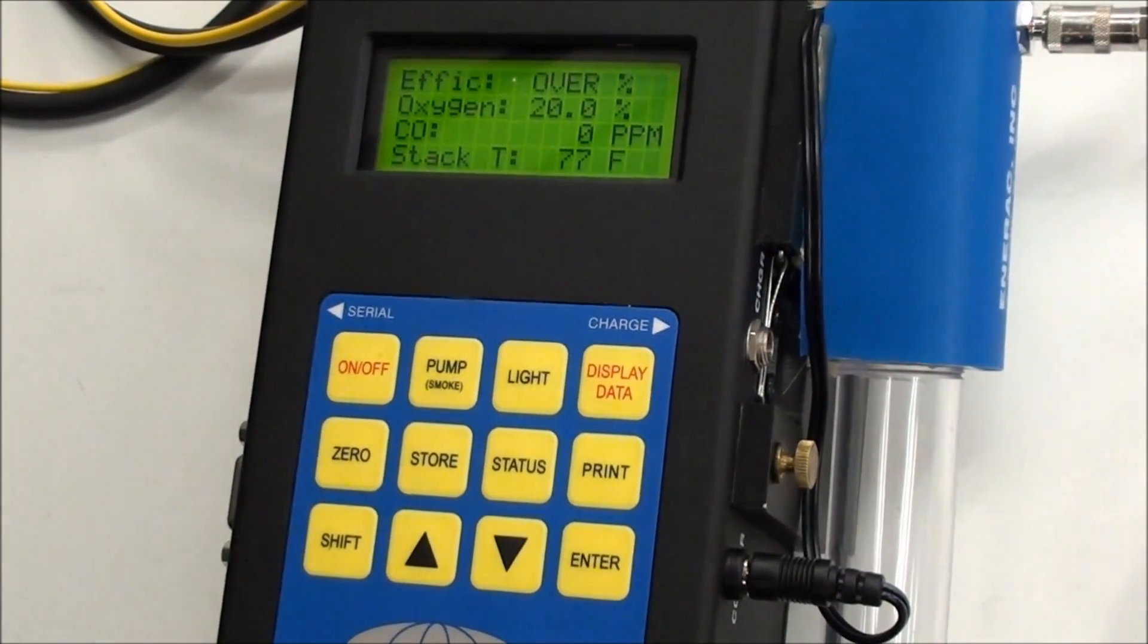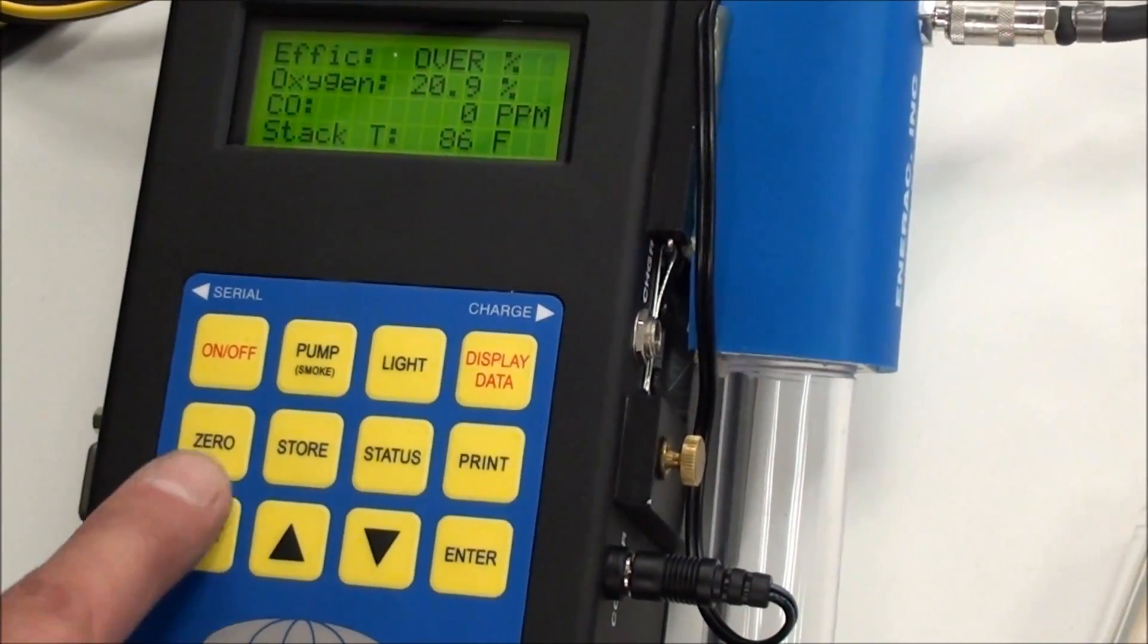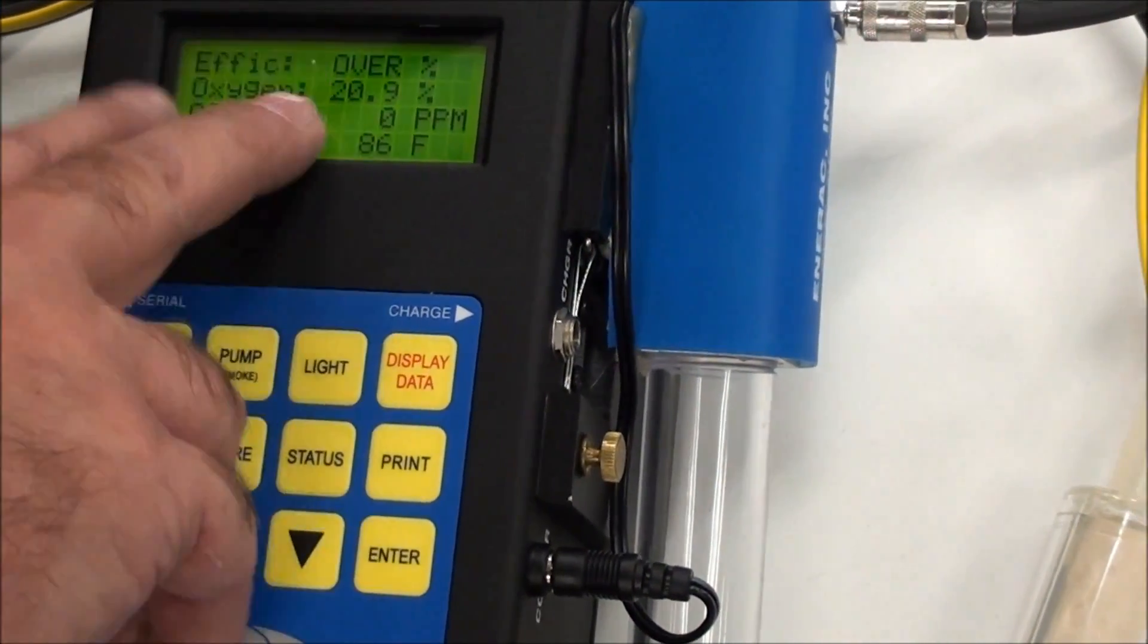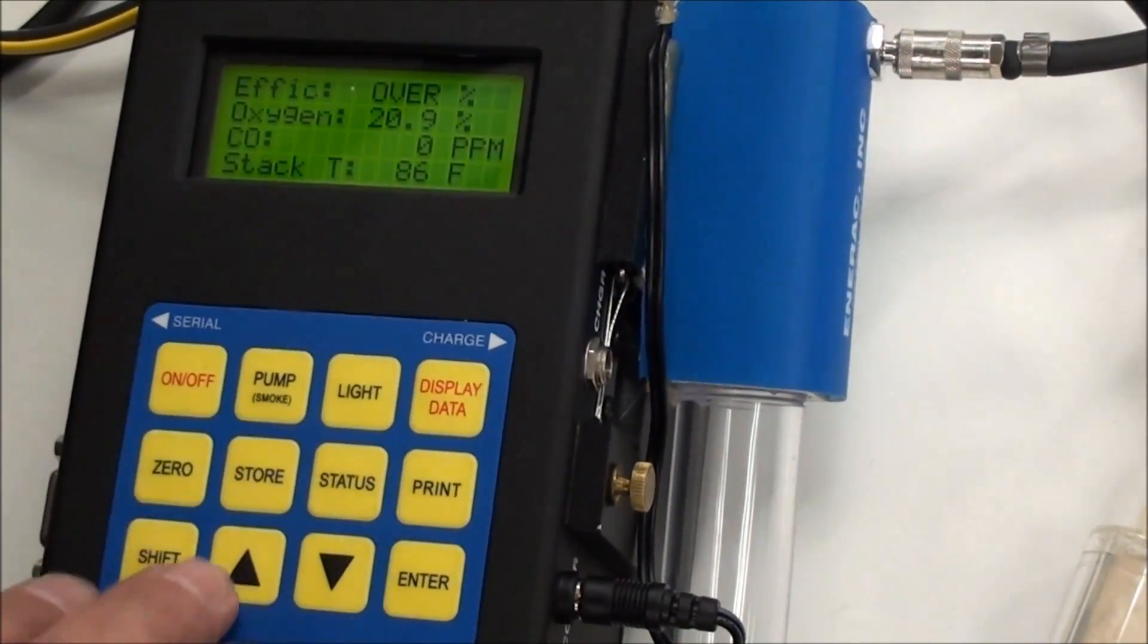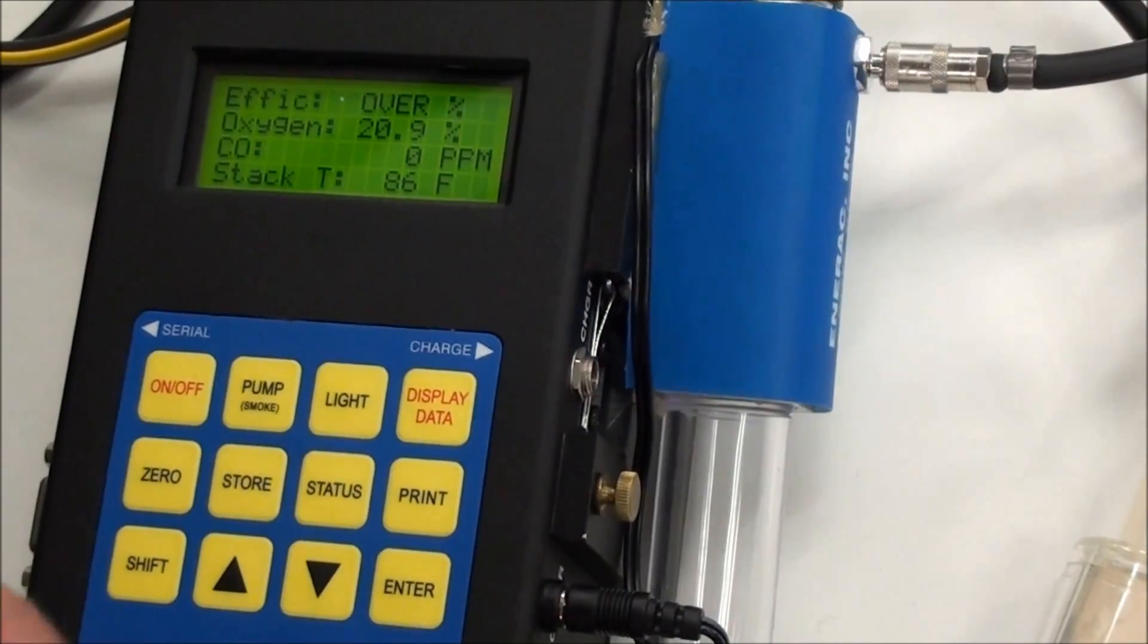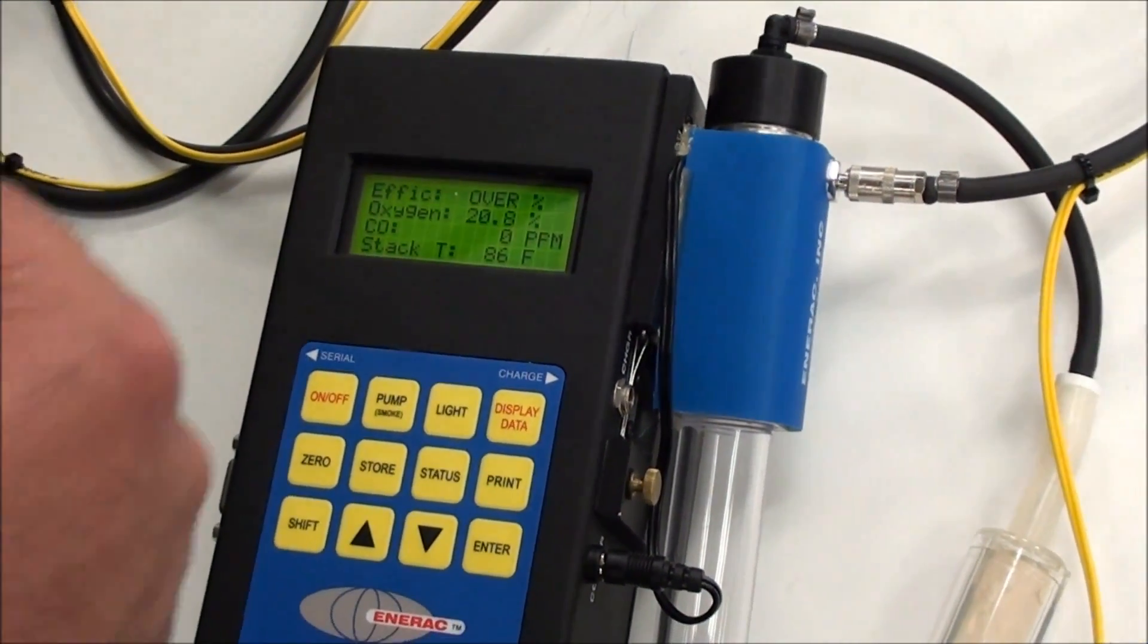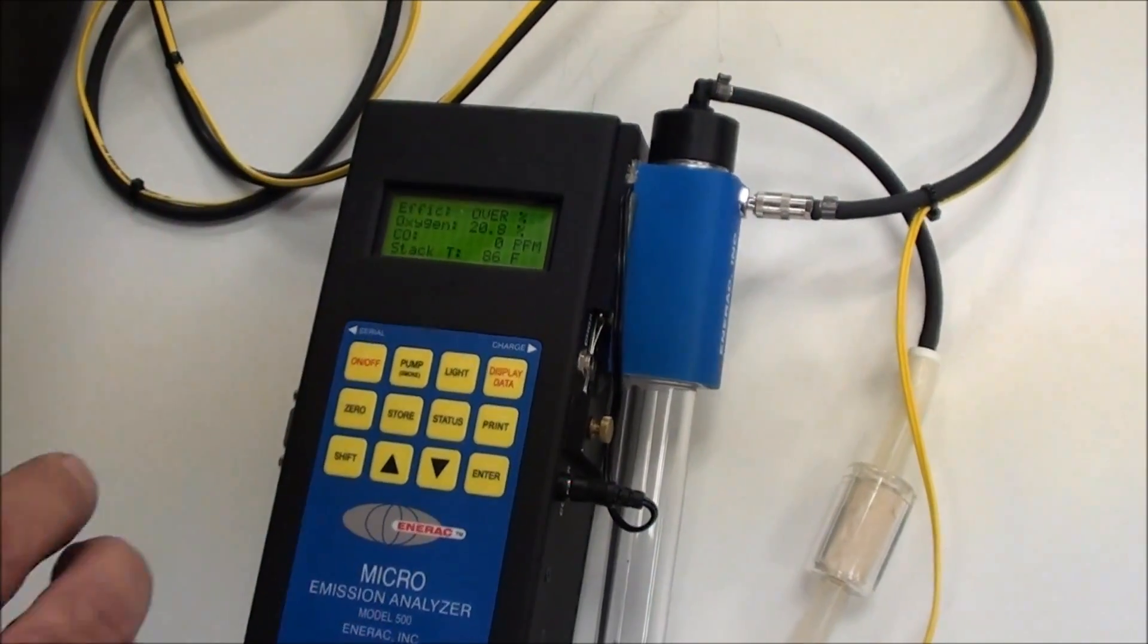Take it out there, let the unit run, and then run your zero. You run the auto zero by pressing the zero, and then enter, and you will see a countdown. It will count down from either 120 seconds or 180 seconds, down to zero. At the end, it will zero all the sensors.